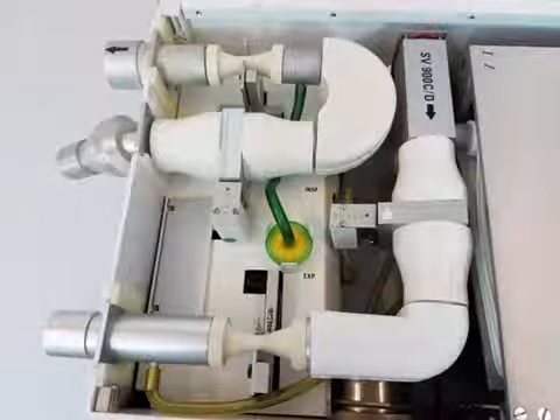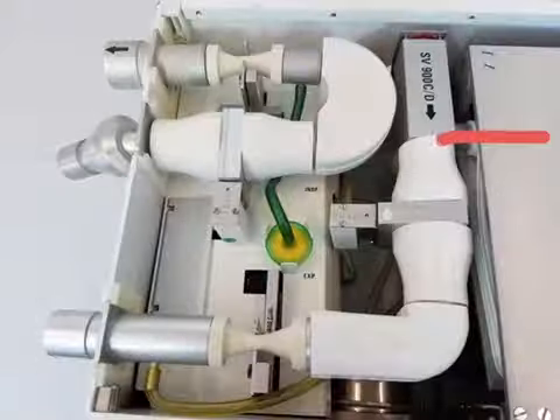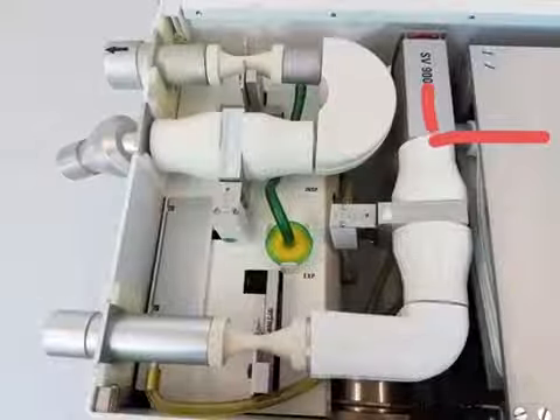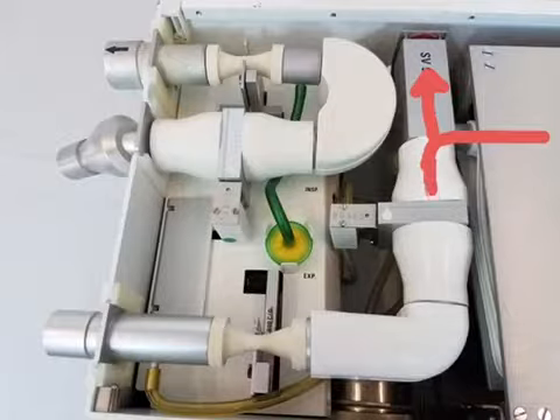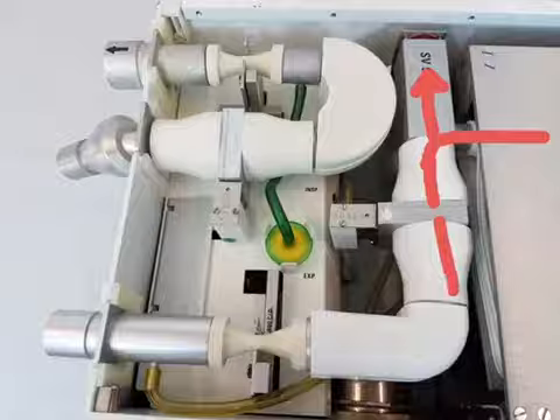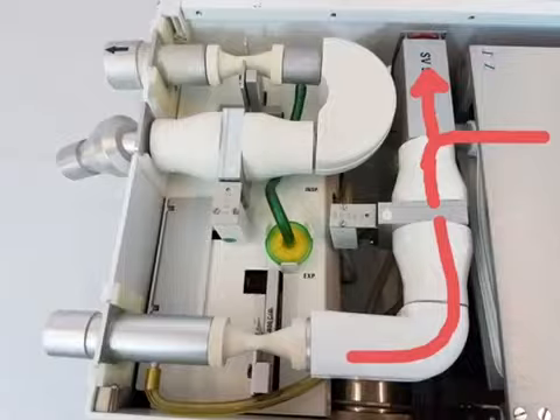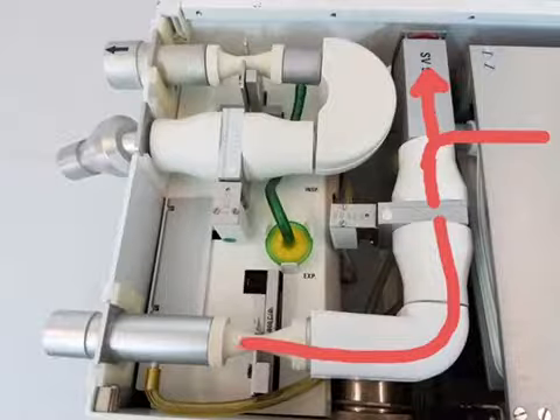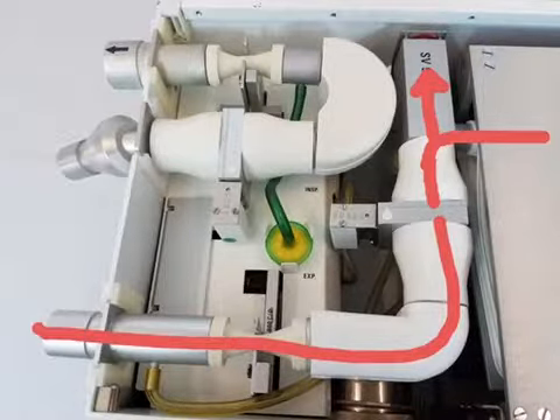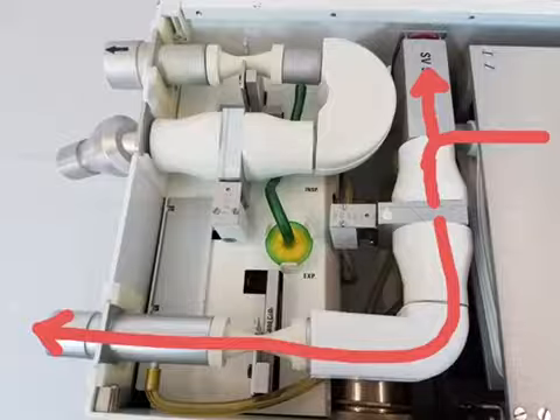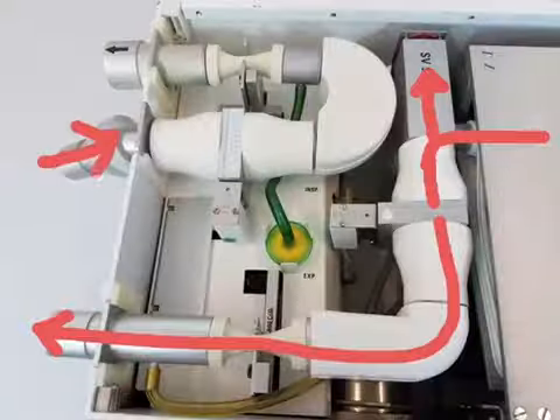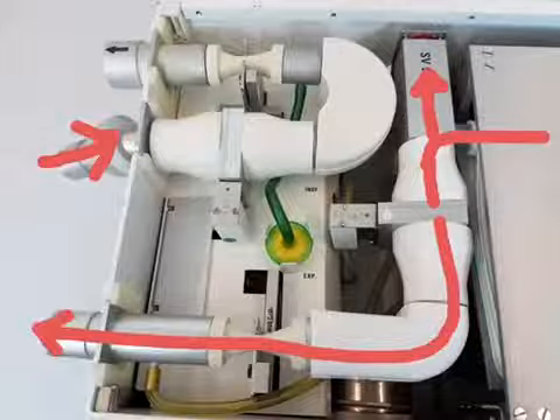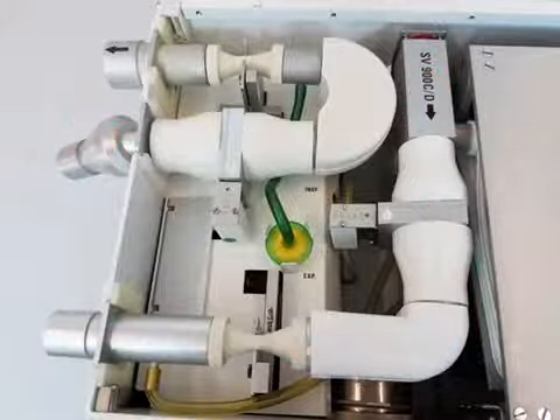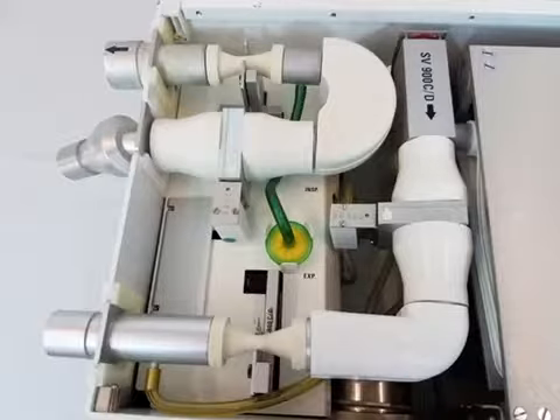Now let's trace the gas flow pattern. From the bellows, it's going to go through here. If the pressure is too high, it's going to go out my safety valve, but otherwise it's going to go the path of least resistance through here, and then it's going to loop around, go through my inspiratory valve, and then it's going to go out to the patient. Now let's talk about gas coming back from the patient. It's going to come in on my expiratory side. The first place it comes into contact with, it goes through the tube. It goes here.